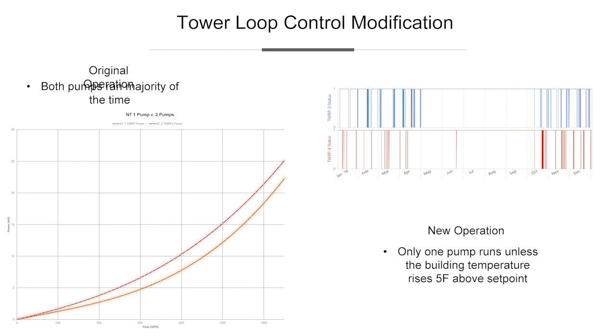Put the ultrasonic flow meter on the system, stage the pumps, watch, observe, discover that at best, that second pump was bringing the system to about a 1.25. And in reality, for the conditions of the area, it became more and more evident that there is never a reason for that second pump to have run, ever. It really could just go to lead lag. So we go into the system, we change the code, we change the programming ourselves, and get them that efficiency of that second pump being removed from the system.